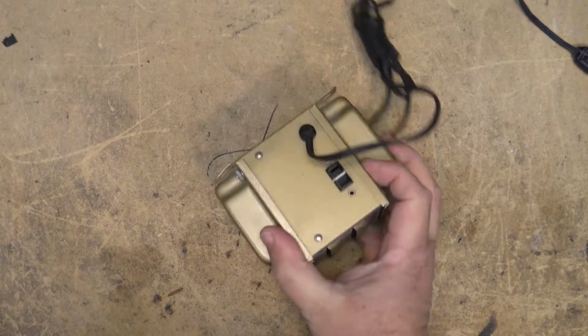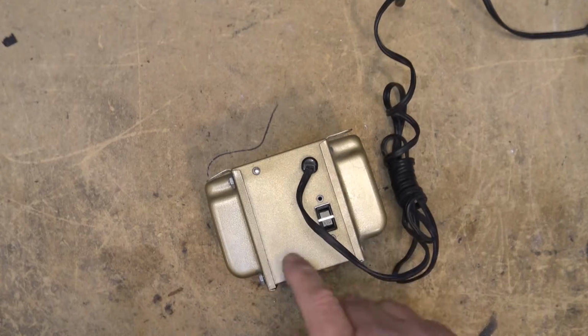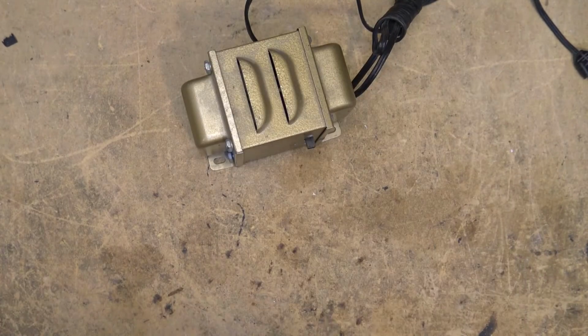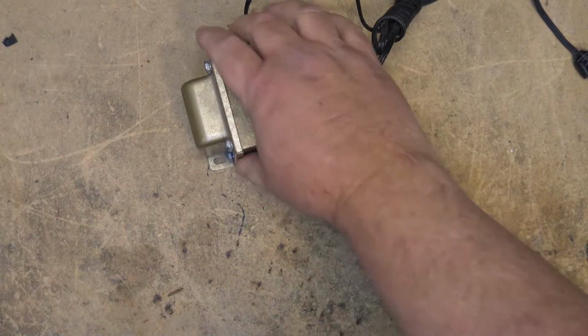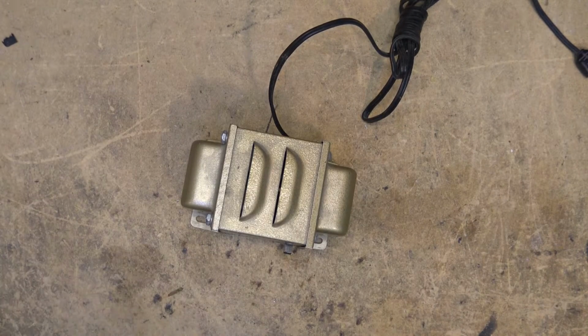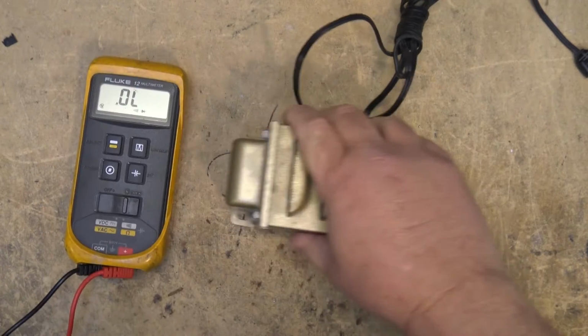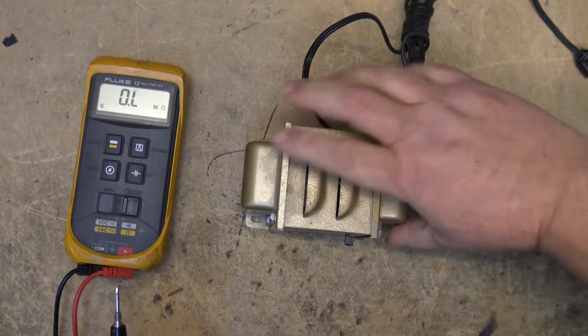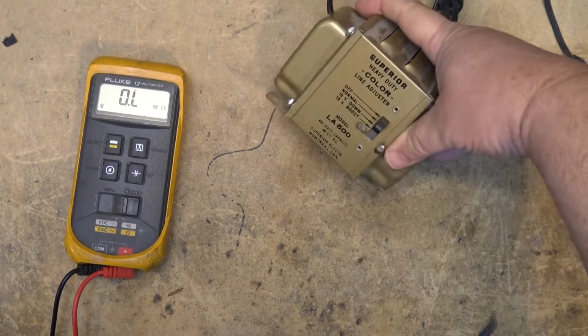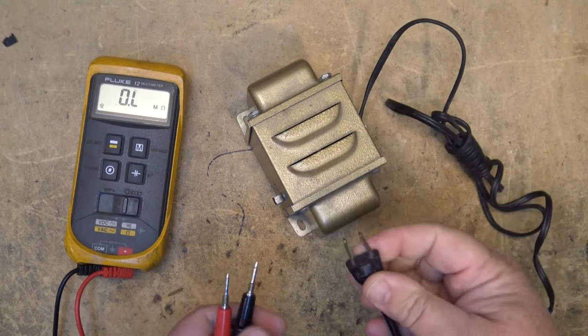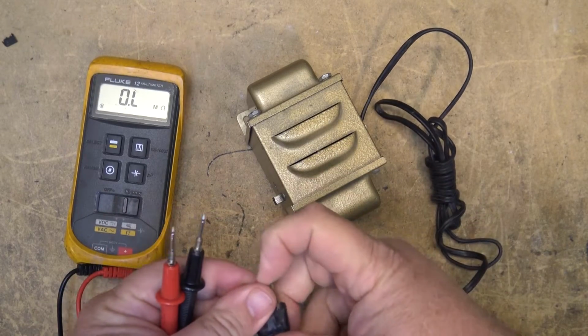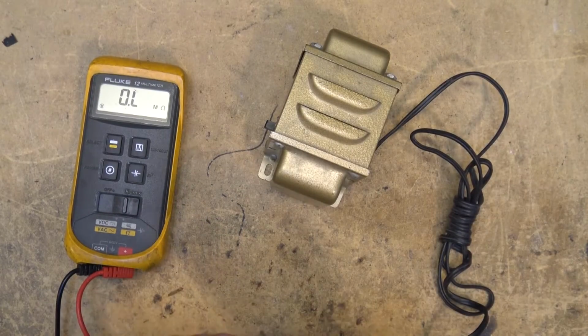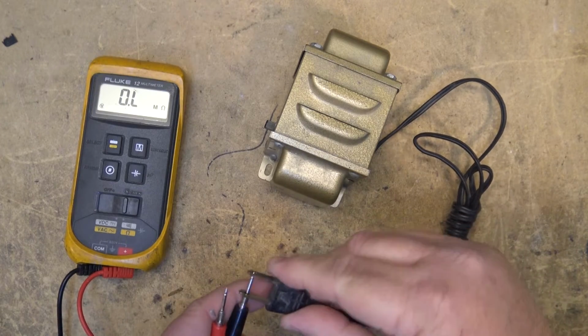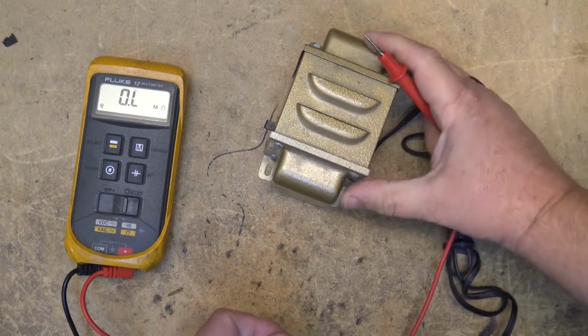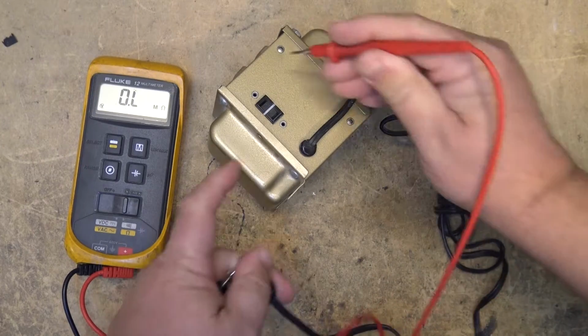And I got to thinking, this is the transformer, but is this an isolation transformer? Is the output isolated from the input? It's possible it could be a full isolation transformer, but it might not be. How we're going to determine this is we'll just take the meter and measure between the electrical plug, which as you can see is not polarized, and the output. Let's measure both pins and see if either one has continuity, because we should have no continuity at all.